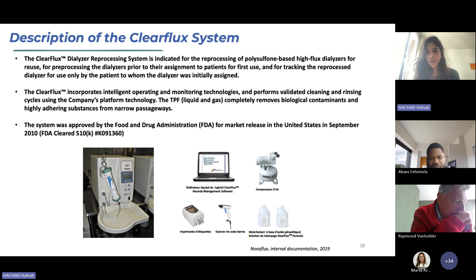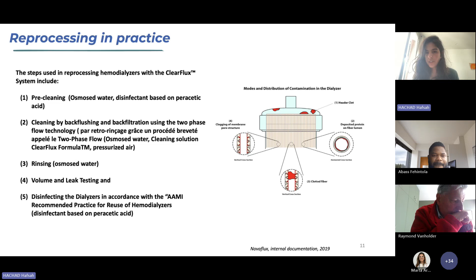And so the steps used in reprocessing hemodialyzers with the ClearFlux system include the pre-cleaning that uses osmosis water and disinfectant. Then you have the cleaning by backflush and backfiltration that uses this specific two-phase flow technology. As you can see, it cleans the membrane with the reverse ultrafiltration of pressurized cleaning liquid from the dialysate side of the dialyzer, while simultaneously supplying hyper-pressured air to the blood side. And this generates a two-phase mixture in situ that completely removes all the deposits of protein and the clots.